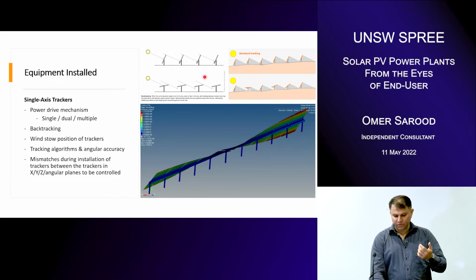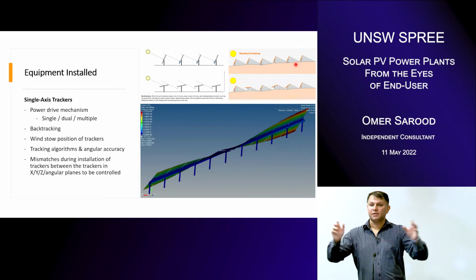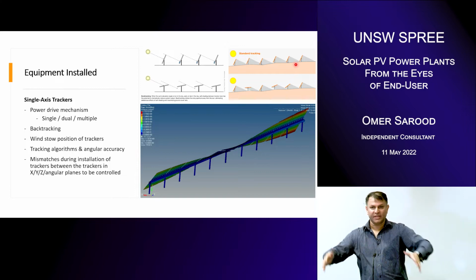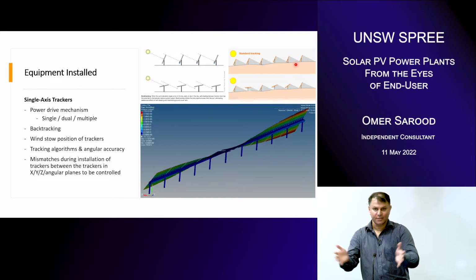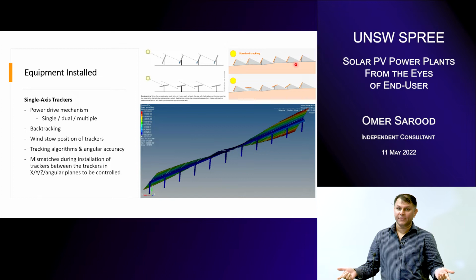Backtracking and how these companies are making use of it. So if you see these two images, what I'm trying to show here is that in standard tracking, all trackers will, well, by the way, most of the trackers are following an algorithm. They don't have an active device that is actually tracking the sun. Based on the latitude, longitude, and other details of the exact site, there is an algorithm which is built into their system, and the tracker starts operating.